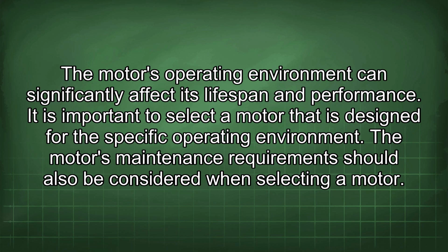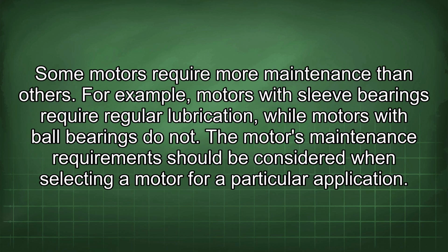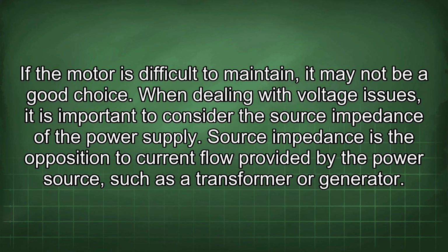The motor's maintenance requirements should also be considered when selecting a motor. Some motors require more maintenance than others. For example, motors with sleeve bearings require regular lubrication, while motors with ball bearings do not. The motor's maintenance requirement should be considered when selecting a motor for a particular application. If the motor is difficult to maintain, it may not be a good choice.